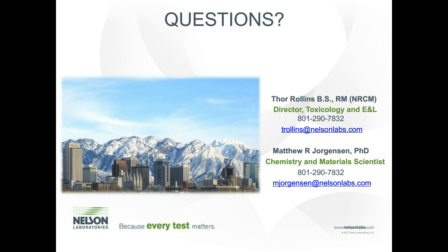Yeah, so that is a very good question. First off, I want to make sure you understand that there's a difference between material and chemical. Even short-term contact devices need to evaluate their materials for risk. But the chemical characterization, like I talked about in my presentation, is most likely able to be used with the prolonged or permanent contacting devices outside the big three. That being said, I don't want to say that you cannot use chemistry for some of those endpoints, depending on the material information you have.